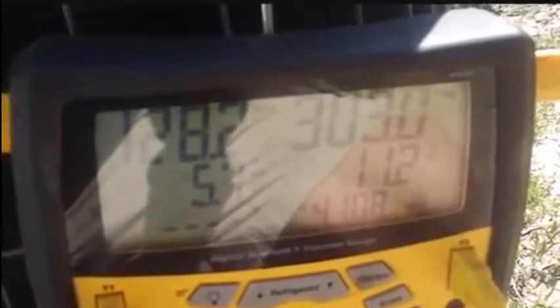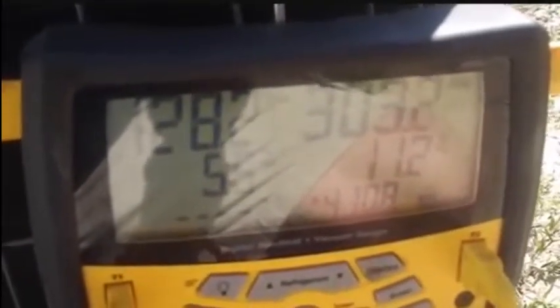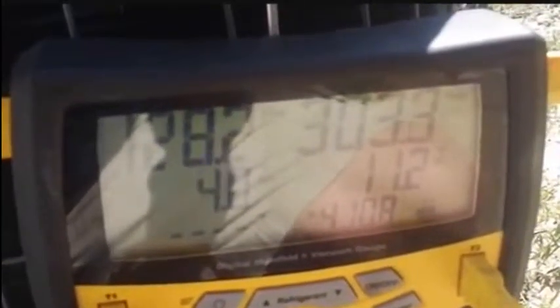Well, our target superheat was 13, and we've been up to 13.5 down to 11.2. It's going kind of back and forth. So we're doing pretty good. You see the TXV's adjusting, changing the superheat. So subcooling's bound to be around 5 to 8 degrees. So I'm pretty happy with that right there. It's on the lower end of the spectrum, but as long as it doesn't drop down too much farther, I'll be happy.